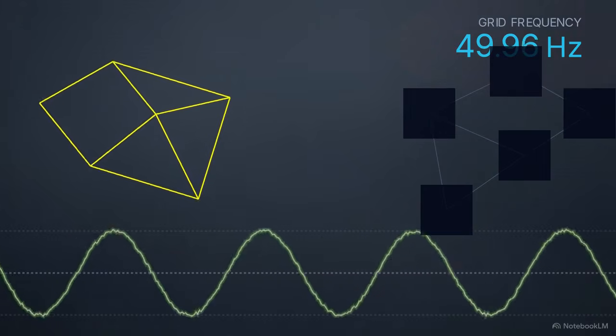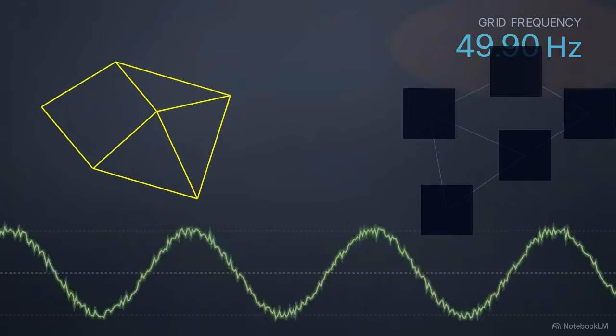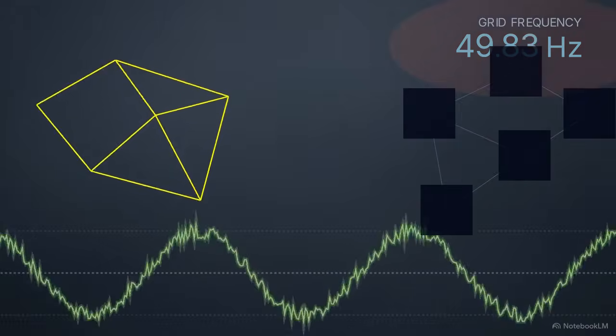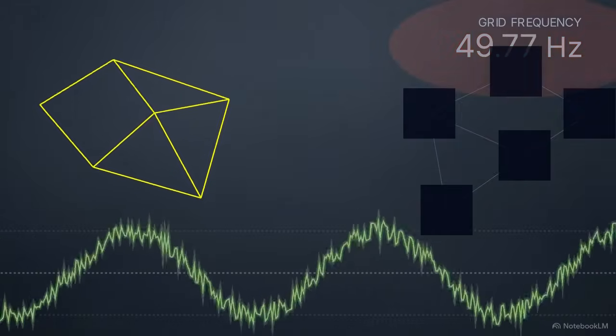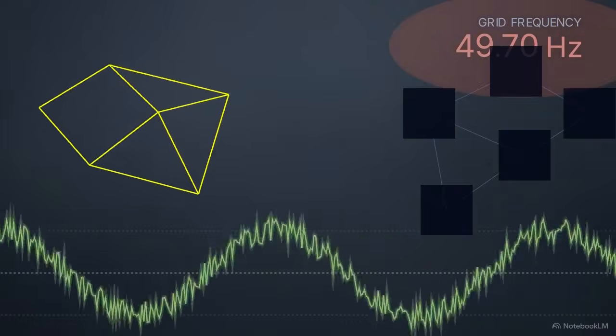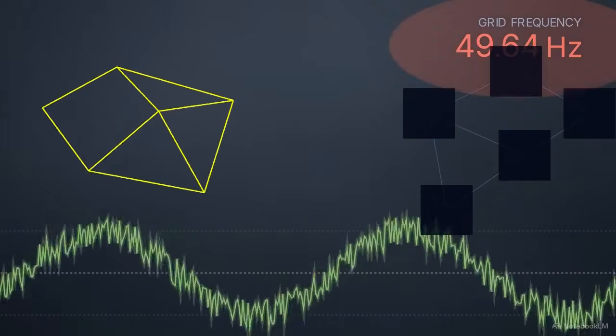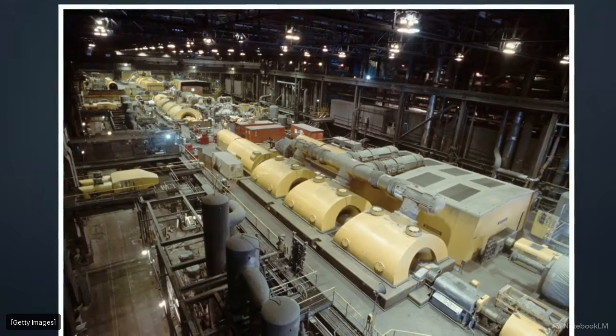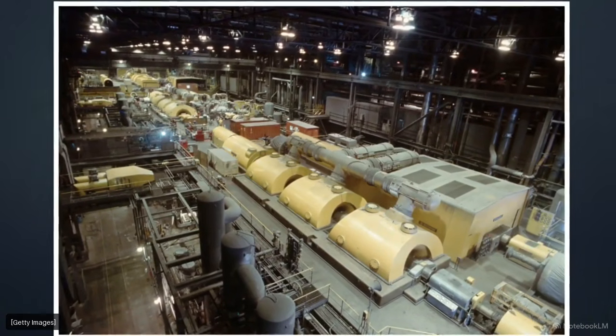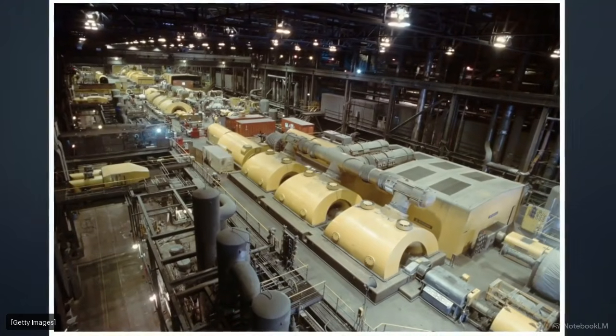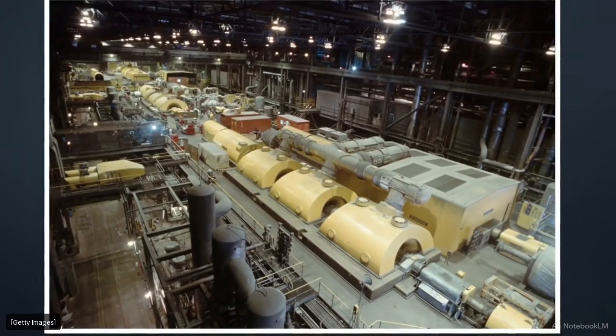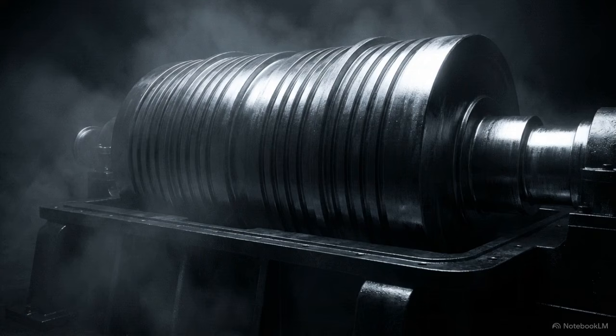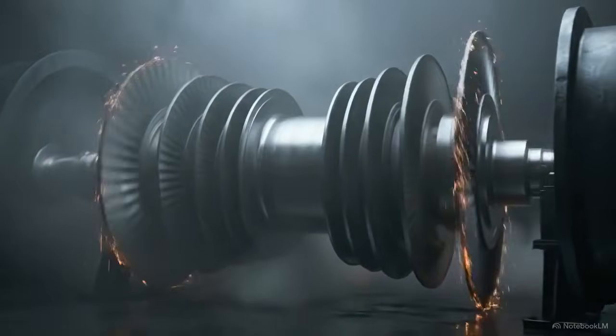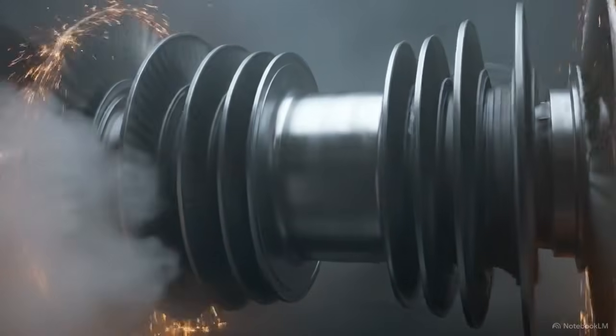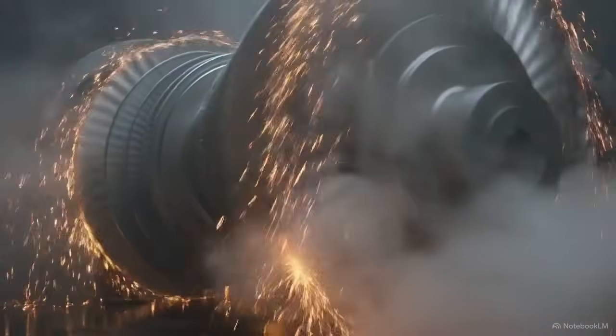This imbalance causes the grid's frequency to plummet. Frequency, measured in hertz, tracks how many times alternating current changes direction each second. At 0.09 seconds, the rhythm is dropping rapidly below its required 50 or 60 hertz baseline. To prevent a collapse, the grid relies on inertia. Traditional power stations generate electricity using 100-ton steel rotors spinning continuously inside these massive turbine casings. Because these heavy rotors are already in motion, they naturally resist slowing down.